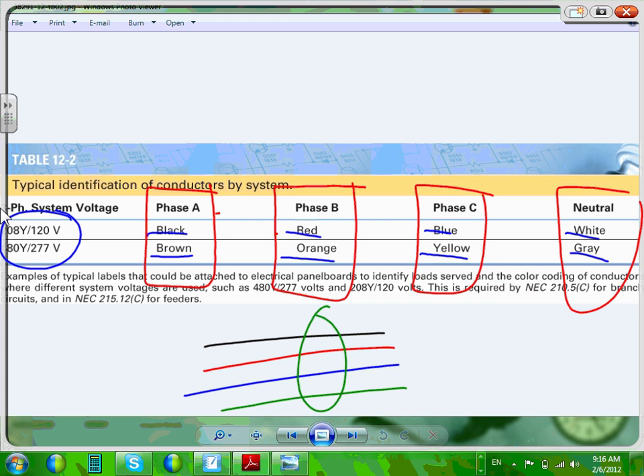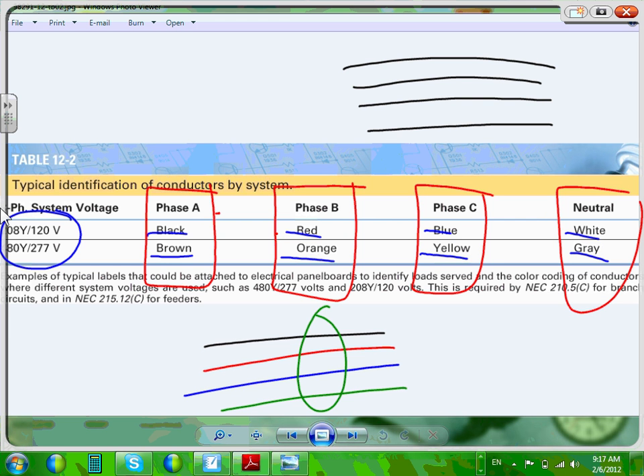And then the other option, for conductors larger than number 4, they start actually coloring. This is color-coded conductor. They start with the system, phase A, phase B, phase C, and a neutral, right? One color conductor. And guess what they do with the color? They identify them. This is phase, let's just say this is phase A, phase B, and color on both sides, right? So I'm identifying it with tape at the end, wherever I have access to it, and then another phase C. Can you guys see that?